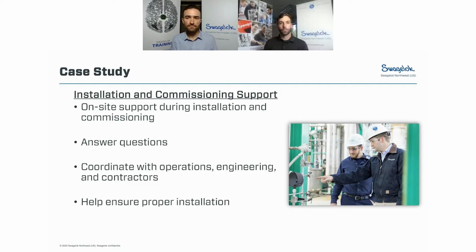And with that, what we find a lot of times when we go out and review systems is that the system itself or the subsystem was often designed and built to high quality standards. And then the installation is where something gets missed. Inlet and outlet are swapped, or in the tying in of the system, a few steps are skipped. So that's why we try and make sure that by being on site, we help to ensure that the system is properly installed and the process is followed as designed.